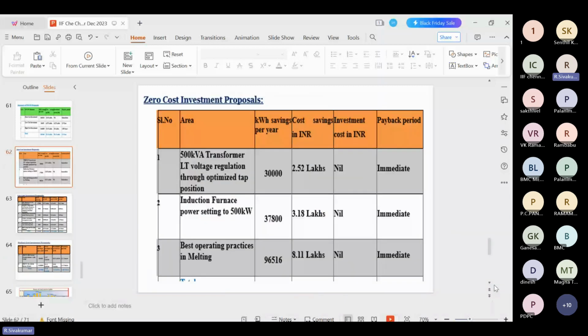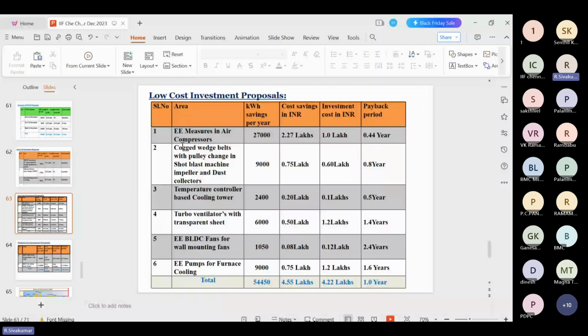Energy efficiency measure in air compressor, and the cogged wedge belt with the pulley change in shot blast machine, impeller and dust collector. We already touched upon this belt area in the last webinar. Here there is more wobbling and more slippage. That's why the shot blast machine timing is increased to 12 to 15 minutes per batch. Actually, it should run around 5 to 7 minutes only. So the cogged belt and the pulley change means they are able to save almost 9,000 units per year. The investment needed is 0.6 lakhs, cost saving is 0.75 lakhs, and the payback period is 0.8 year.